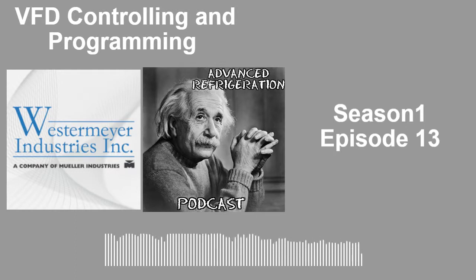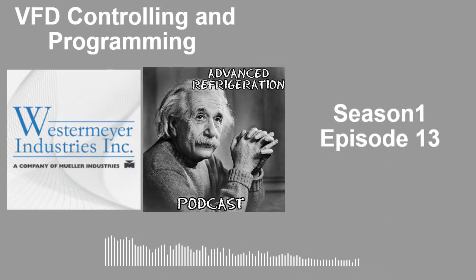So, I mean, this is a similar thing you're going to see 99% of the time at most Walmarts. Not every Walmart, like some of the newer stores went back to non standalone drives, but most of those Walmart and Sam's stores have these Danfoss drives or a Control Techniques, which is NIDEC now, VFDs, and they're using those to control their condensers. They work extremely well when they're set up properly. Most of the time when you're having issues with them, the setup's not right.